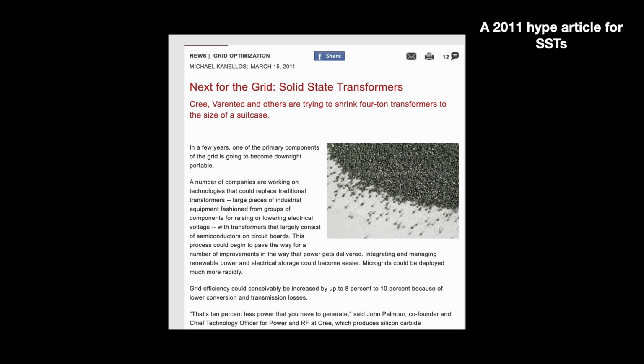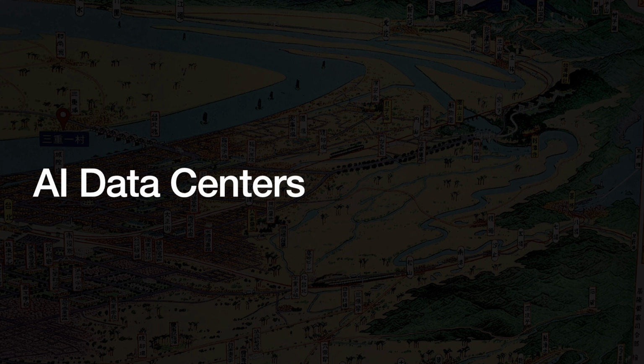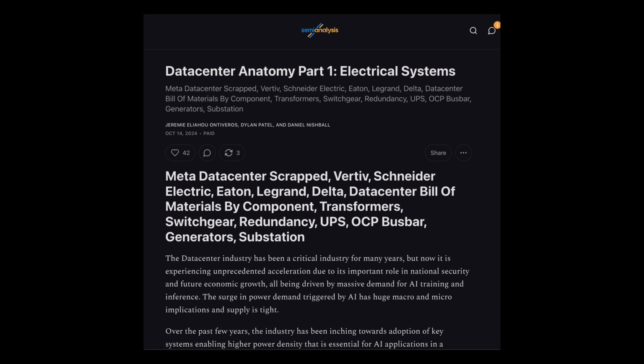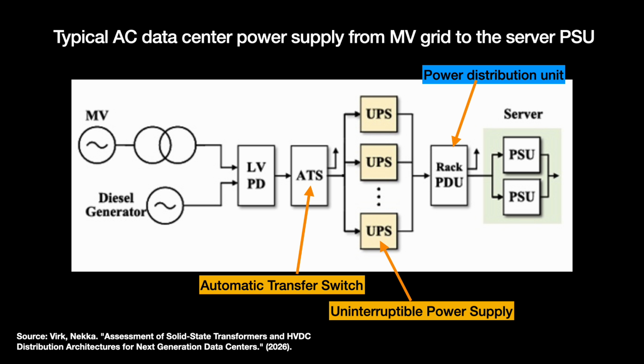Time for us to talk about AI data centers again. A major shift in these data centers has to do with their power usage. I'm not going to spend a lot of time explaining this, there are big semi-analysis articles you can read instead. But traditional data centers receive medium voltage AC power from the utility and run that through a hierarchy of systems, including two sets of transformers and an uninterruptible power system, UPS, to get the DC voltages suitable for the chips.